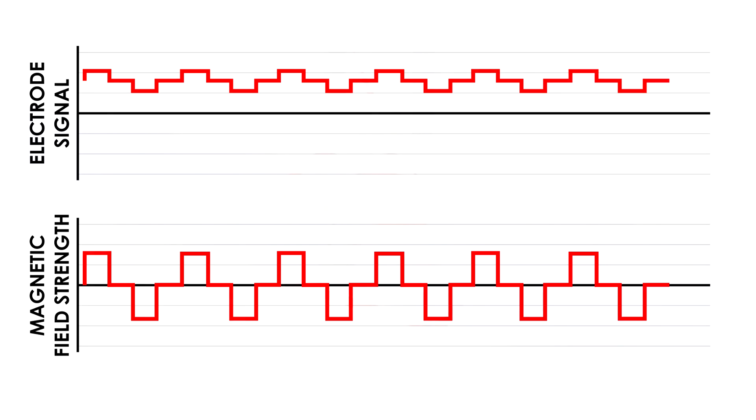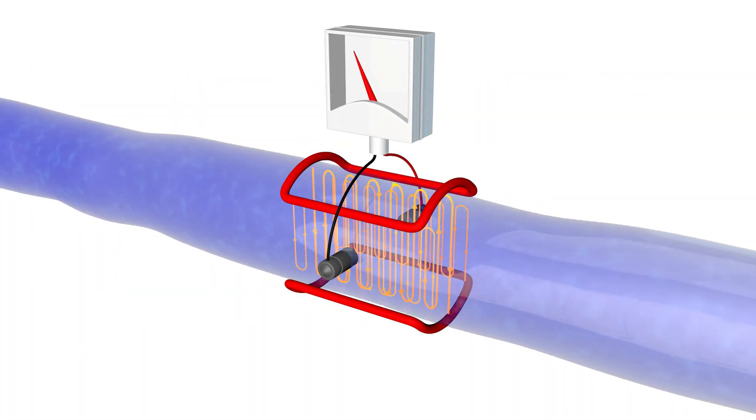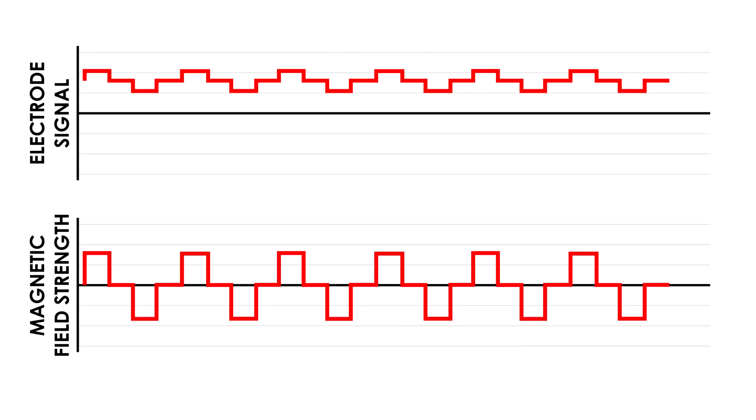Remember, we only care about the portion of the EMF generated by the magnetic field, since this is the only part of the signal which is proportional to the velocity of the fluid. Everything else is just noise. Notice that even when there is no magnetic field, there may still be a non-zero voltage between the electrodes.